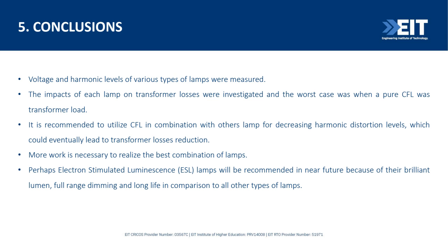The worst case was for pure CFL in terms of the transformer load. It is recommended, at that time, to utilize CFLs in combination with other types of lamps to decrease the harmonic distortion levels, which could eventually lead to transformer loss reduction.